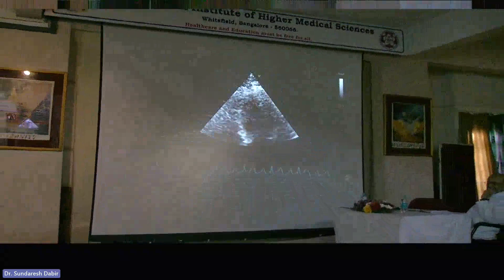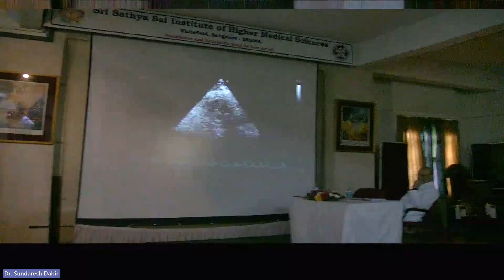What happens to spatial resolution as transducer frequency goes up? Spatial resolution goes up with higher transducer frequency, right? So if I want to see something small in this LV apex, I want a high transducer frequency. So what I do is I just go to my machine setting and I increase the transducer frequency. Okay, got it? Understand?